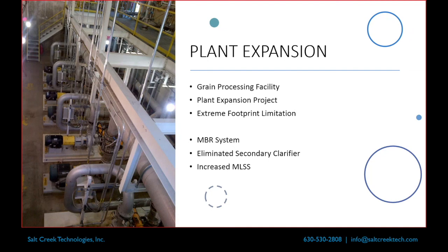So again, we did the full conversion of the secondary clarifier into a membrane system, and now they're generating a fairly nice effluent stream that's fairly ready for reuse.